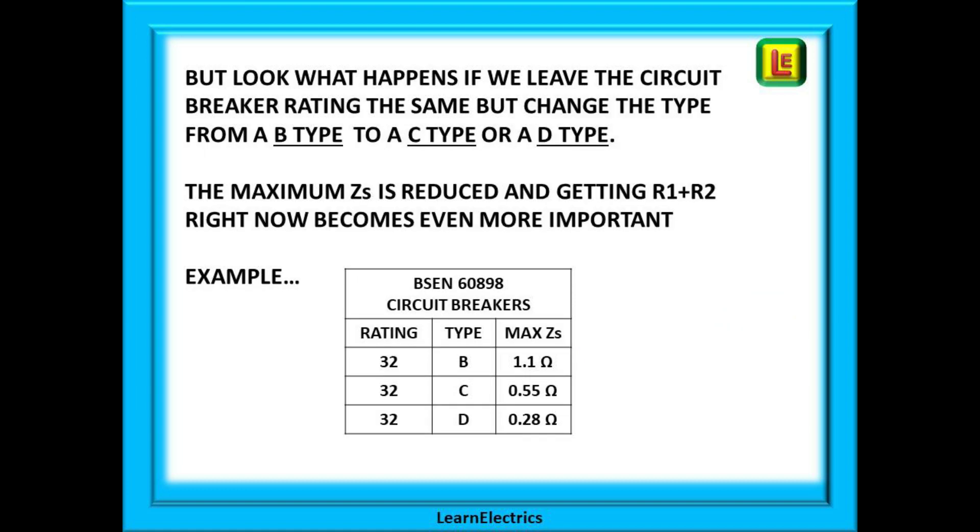But wait, we cannot just change any breaker for any other. ZS rules must be followed. Look what happens if we keep the rating the same but install a different type as C or D type. Some electricians would change the popular type B breaker for a type C where the customer complains of the breaker nuisance tripping. If you change to a type C, the permitted ZS goes down. It is now even harder to get the figures to match and cable lengths and sizes become more critical. And changing to a type D breaker makes it worse again. So please be aware of the effects of changing breaker sizes. It can sometimes work in your favour and sometimes against you. We must always think of the user's safety if something goes wrong.